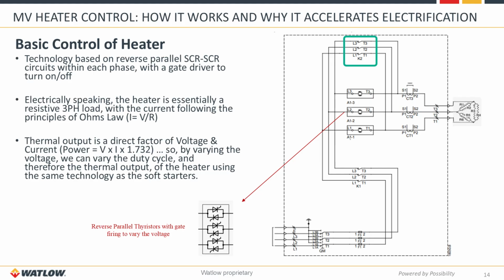So in the motor soft starters, you have this bypass contactor up here in the upper part of the diagram. You no longer need that within a control system for a medium voltage heater. We can eliminate that particular contactor and just use the soft starting technology of the thyristor in order to power the unit. So the output power that you get from the heater itself out here would be the voltage, whatever voltage you're giving that, times the current, times the square root of 3. You get 100% efficient power conversion from the electrical power that's given to the thermal power into the system.